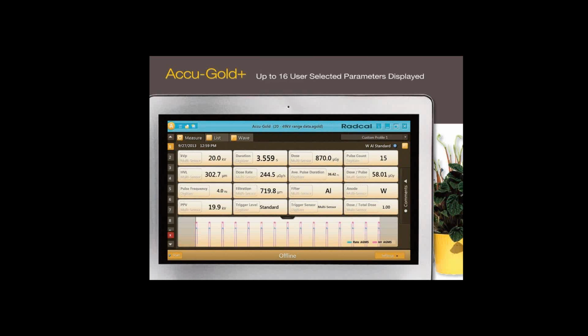In front of you, this is a previously measured session. Here you can see 16 different parameters measured for each exposure. This happens to be a tomo mammo exposure. Note that the waveform is also displayed for each measurement. This is not a portion of the waveform, but the entire waveform from start to finish. Accu-Gold+ can capture a waveform up to 300 seconds or 5 minutes in length.